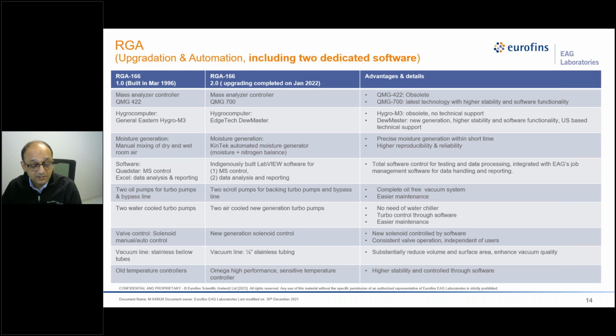There are big changes to the vacuum system. We had oil pumps and old turbo pumps which were water cooled. We removed them and put in scroll pumps, which are dry. There is no oil in those pumps. We also moved away from the water chiller part, so we don't have to maintain them anymore. Our turbo pumps are air cooled. There were some small changes too, while we were doing these bigger changes, to generate a highly stable and reproducible signal strength on the mass spectrometer system.